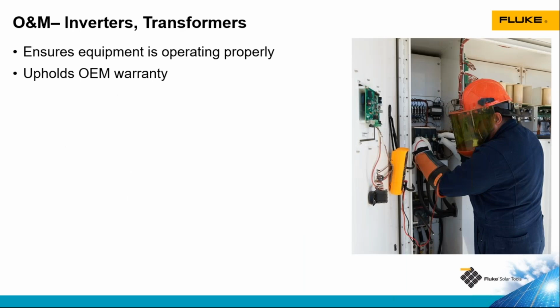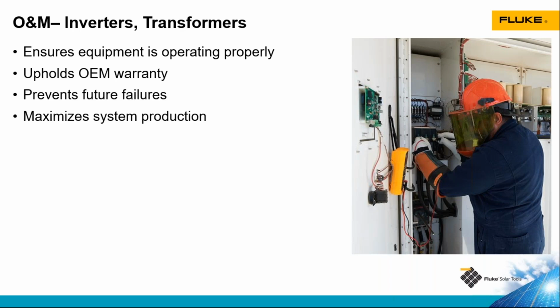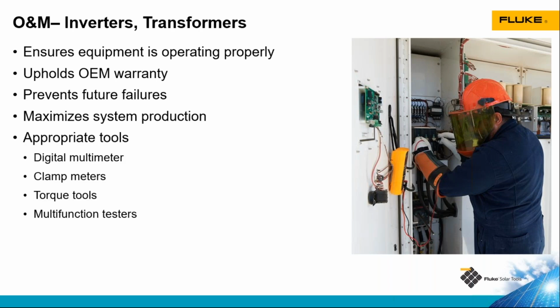We do our operations and maintenance on our inverters because we want to uphold the manufacturer's warranty. The manufacturer is going to have a list of annual maintenance requirements. If we don't do those tasks, then we may void the warranty if there's an issue in the future. Doing preventative maintenance also prevents future failures, makes sure that our system is operating to its maximum potential and providing the financial benefit that the asset owner requires.